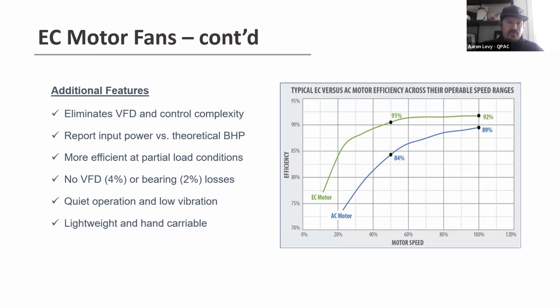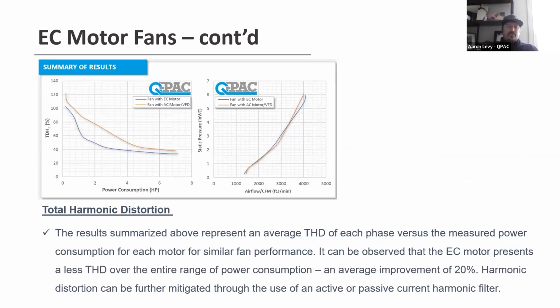Partial loads and slowing them down, you start to see the fall off pretty quickly. EC fans don't tend to have as much fall off until you get about 20% under their RPM speed. Then you start seeing it. But once you start adding a VFD and belts and pulleys, all those losses still come down. The fans are also a lot quieter, and they don't have that vibration that'll vibrate through the chassis. They don't hear the air noise coming back down through the system. So it does make that a lot easier with going to an EC fan type solution.